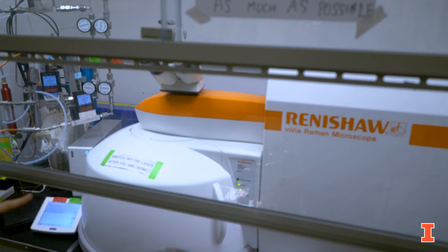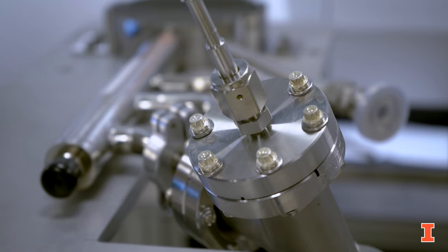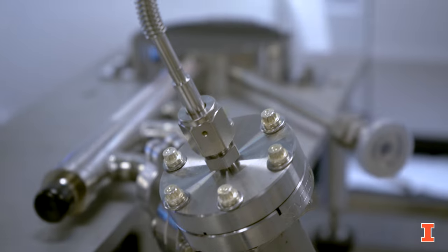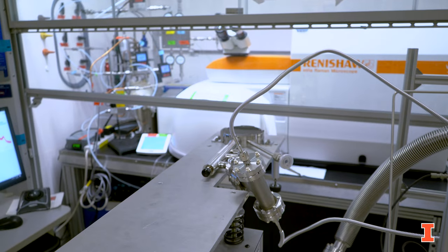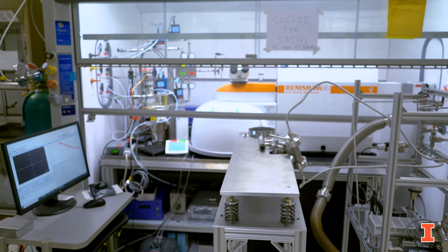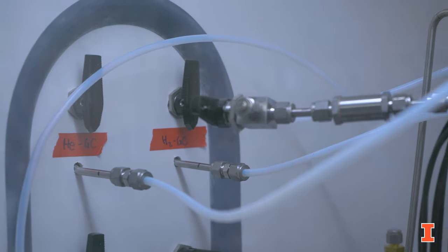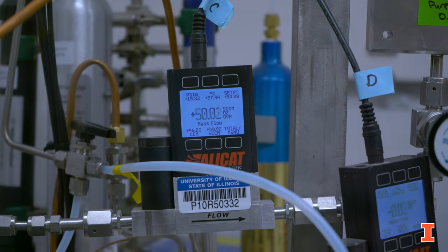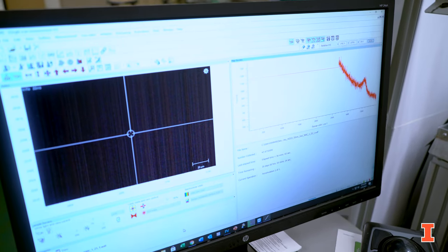One of the biggest challenges of determining reaction mechanisms is identifying surface intermediates under in-situ conditions. We have a Raman spectrometer here equipped with four different lasers — four different wavelengths — to be able to identify different types of surface intermediates on the catalyst surface. We have three types of reactor cells: two are used for gas and liquid phase measurements with temperatures that can go as high as 600 degrees Celsius, and our cryostat here can be used under ultra-high vacuum conditions with temperatures as low as negative 268 degrees Celsius to identify the surface intermediates.